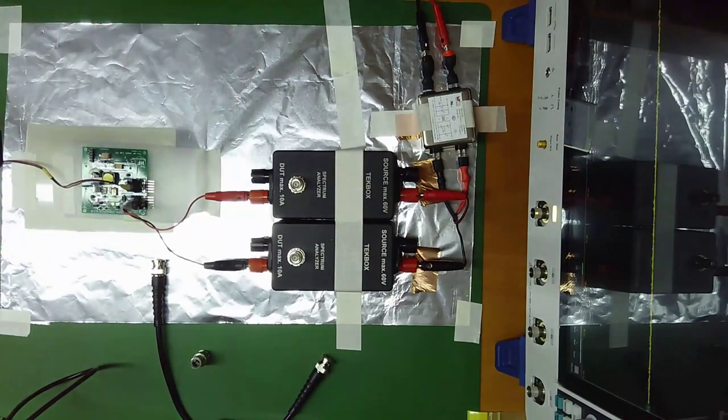Obviously, if your product is inside of a plastic or a metallic enclosure, you need to replicate the full structure to make the measurements. But because I want you to see the internal hardware, I am not using the case of the product, okay?